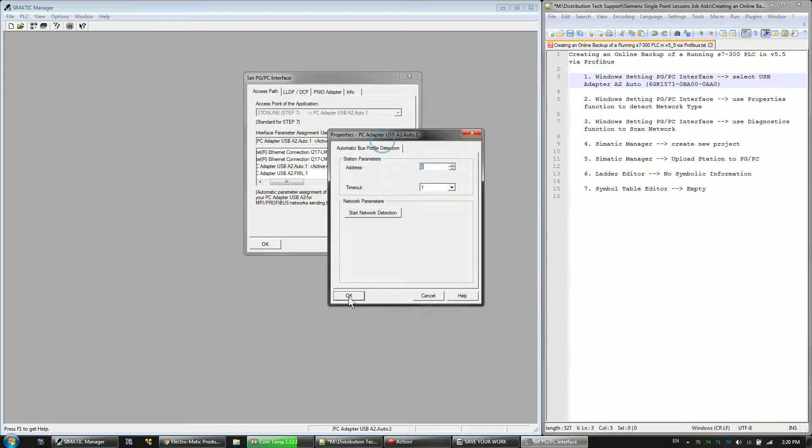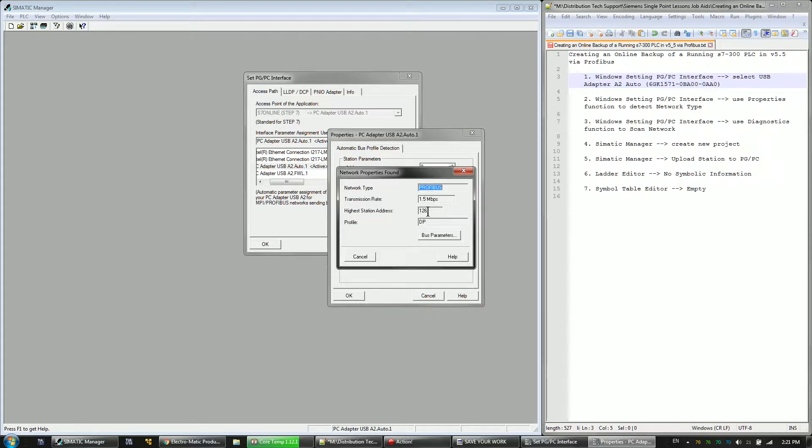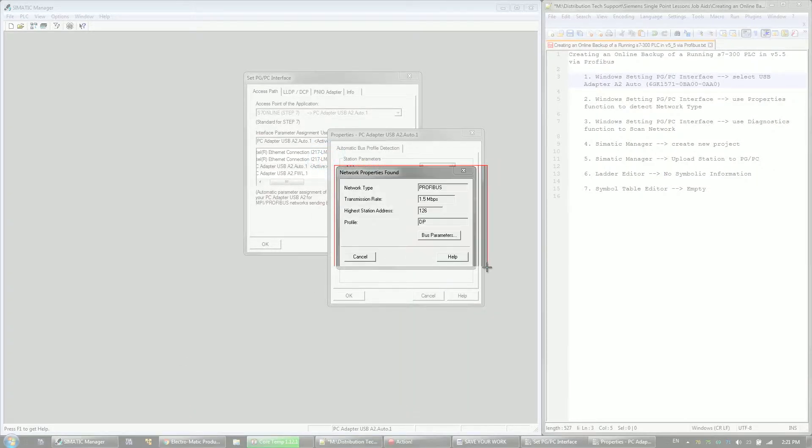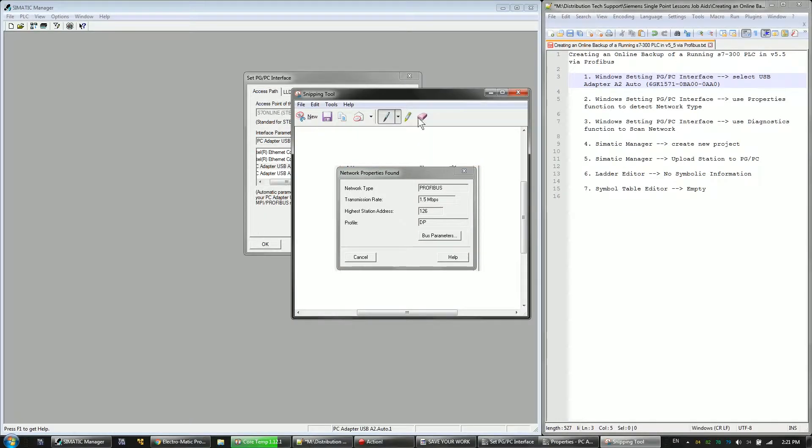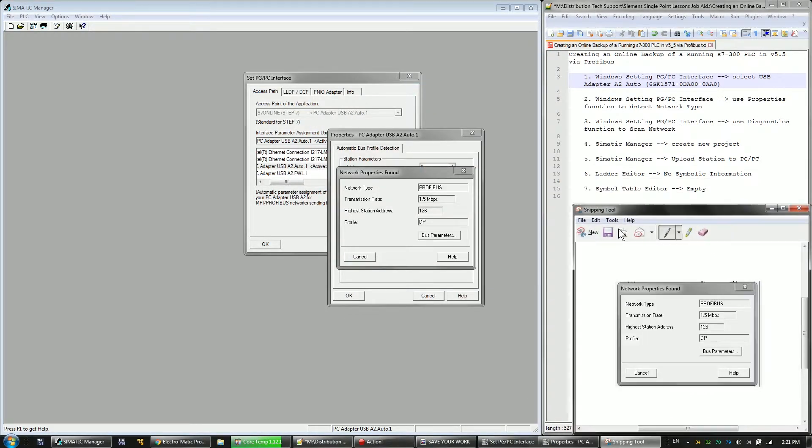Once that's selected, I'm going to go to the properties tool and scan the network. So it says I'm detected to a PROFIBUS network at 1.5 megabaud. That's useful information. Sometimes when you're in the field, you don't really know what kind of network you're supposed to be connecting to. So I'm going to keep that information off to the side here.